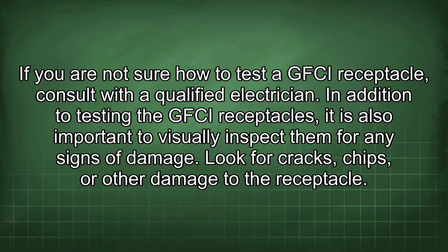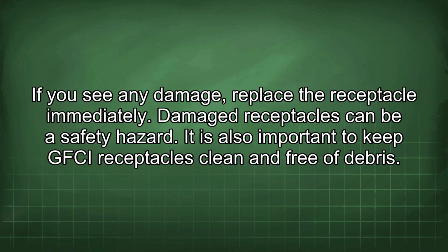In addition to testing the GFCI receptacles, it is also important to visually inspect them for any signs of damage. Look for cracks, chips, or other damage to the receptacle. If you see any damage, replace the receptacle immediately. Damaged receptacles can be a safety hazard.